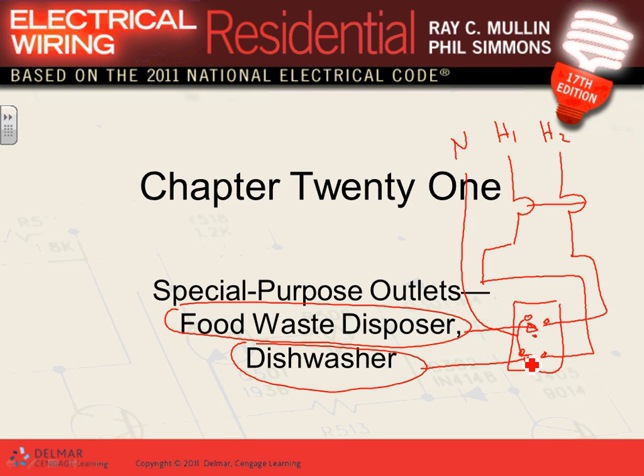That's typical for garbage disposal. So when we design a garbage disposal, typically we assign a dedicated circuit. And we assign a 20 amp circuit here, a dedicated circuit with conductors of 12/3 NM cable. We wired them with 12/3 NMB cable and we gave it 20 amp. That's what we typically do for garbage disposal and dishwasher. That's what you guys did for me in the power, right?